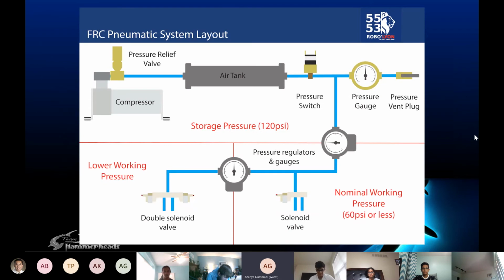Alright, this is just a general overview of how the pneumatic subsystem works and what we just talked about. So the air comes from the compressor, it then flows into the air tank, which serves as storage until we need to use it, and the pressure switch there controls the compressor. And then the pressure regulator decreases the PSI from 120 to 60, and from the other side of that regulator, it powers the solenoid valves, which then move the cylinders in and out. I know that was a complicated section, so does anyone have questions?